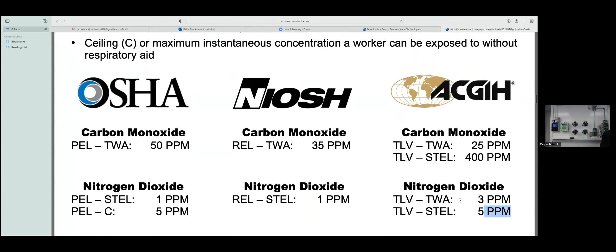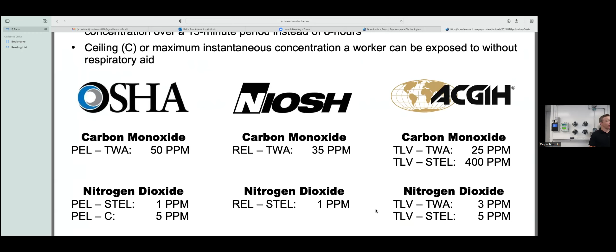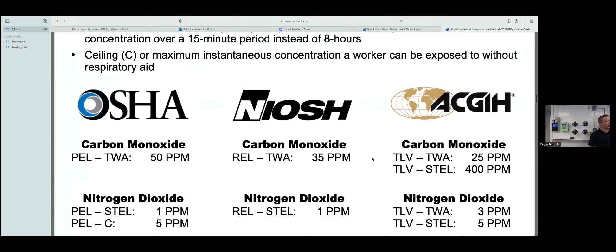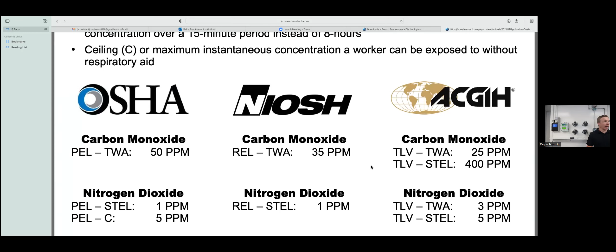So you'll see on here that 5 parts per million is a pretty common mark for nitrogen dioxide. And I would not recommend going any higher than 5 parts per million as a high alert. There have been times where we have seen projects and specifications where 10 parts per million is the high alert value. And frankly, from a nitrogen dioxide safety level, that is too late to be setting off an alarm within a facility. So 5 parts per million is our recommendation on the NO2 and 100 parts per million on the carbon monoxide. Now, as I referenced with Amazon, they also had 12, 25, and 75. So the lower end of that spectrum is very flexible, and you can pretty much configure that however you would like, specific to that customer. But from a high alert standpoint, those are the recommendations based on the safety of the people in those facilities.